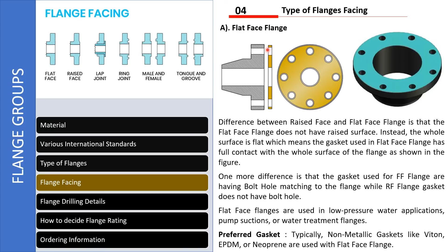The whole surface is there, but at the same time, flat face flanges are not suitable for very tight kinds of arrangements. So we use it where low pressure services are there. For example, low pressure water applications, pump suctions, and mostly water treatment flanges. So flat surfaces are there. Preferably the gasket between these kinds of flanges will be non-metallic gaskets like Viton, EPDM, neoprene. We'll discuss more about gaskets in the gasket section. Here we are just trying to understand the flat face type of arrangement on flange face.